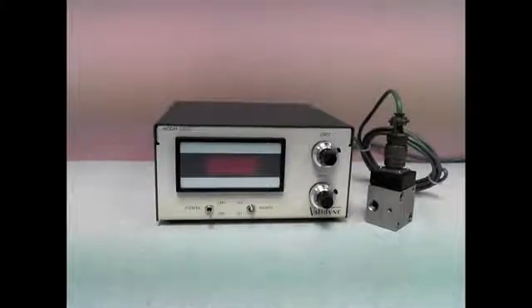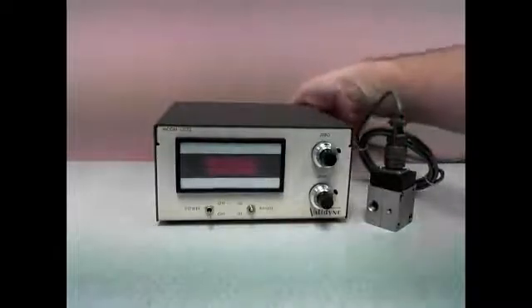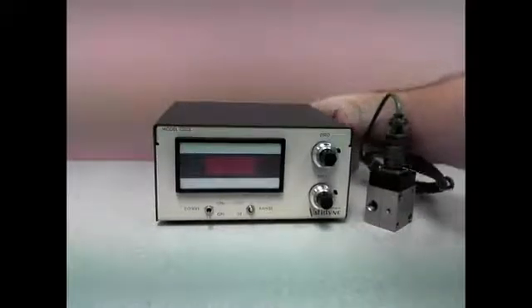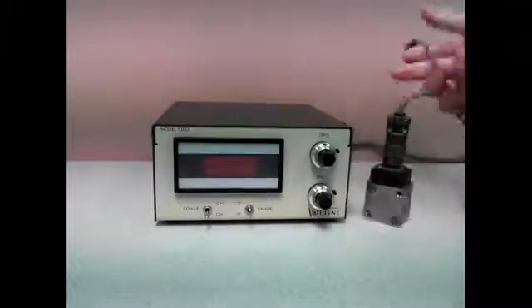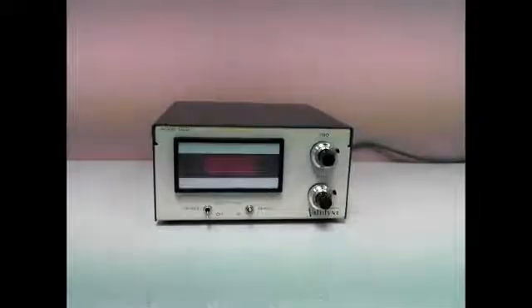In order to check the CD23, we first remove the transducer cable that is connected at the rear panel. If the CD23 has been calibrated with a sensor, write down the dial readings on the front panel zero and span adjustments so that these can be reset later.